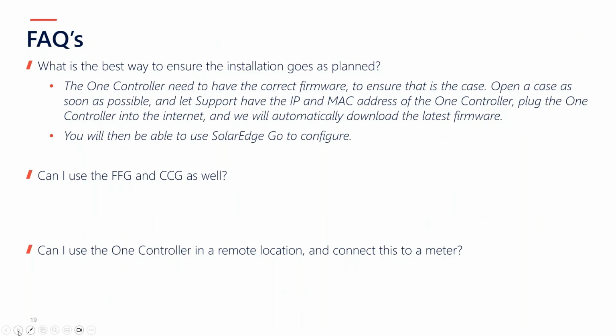Why is that a biggie? Well, it's a biggie if you've got to set a static IP address. So what you can do is configure this in your office or in a hotel room or wherever you are, the night before or the day before, as long as you've got it set up and it's downloaded the firmware. You can configure it to the IP address that the IT department gives you. You put it on there, same as you would an inverter - you go into the one controller, you select static IP address rather than dynamic, and then you enter the IP address that they want you to use.